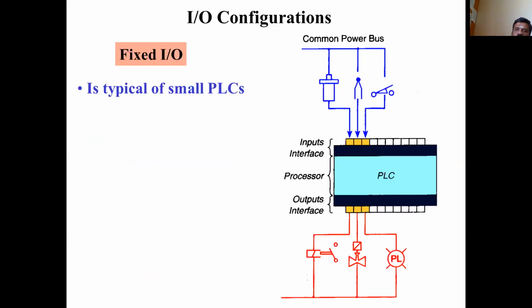In PLCs, there are two types. One is fixed IO, and the other is modular PLC. Fixed IO PLC is a smaller PLC. It will have a limited number of inputs and outputs. So generally, this PLC will be given for training the new ones in the factories, and it will also be used in colleges for student purposes.